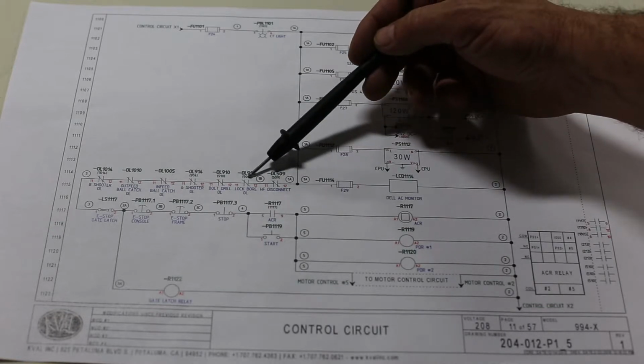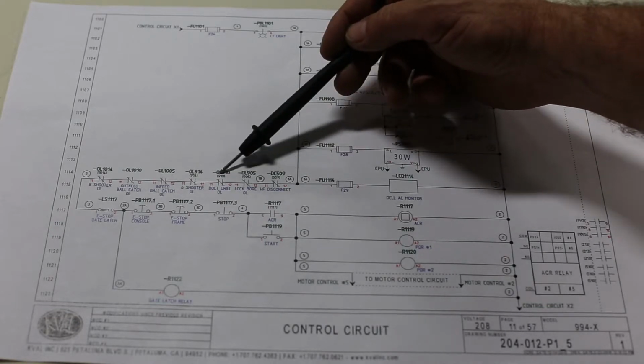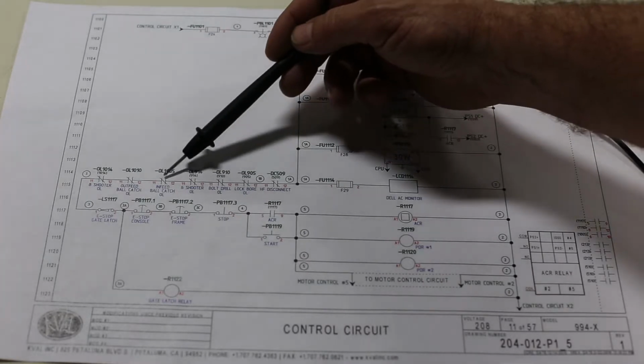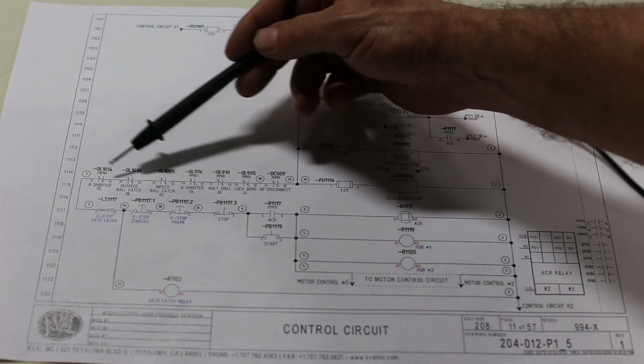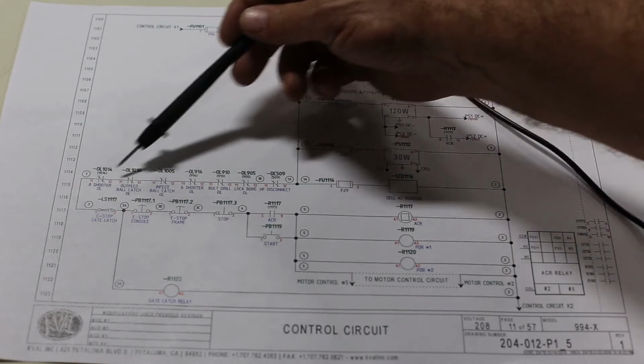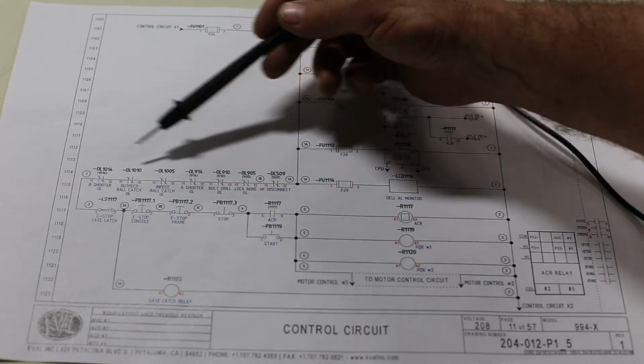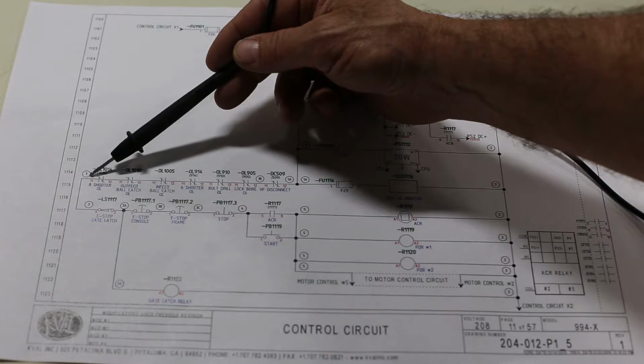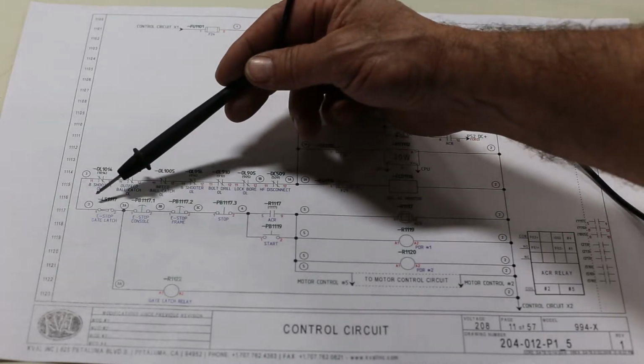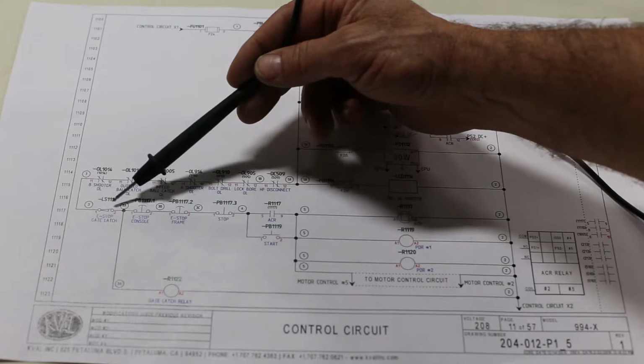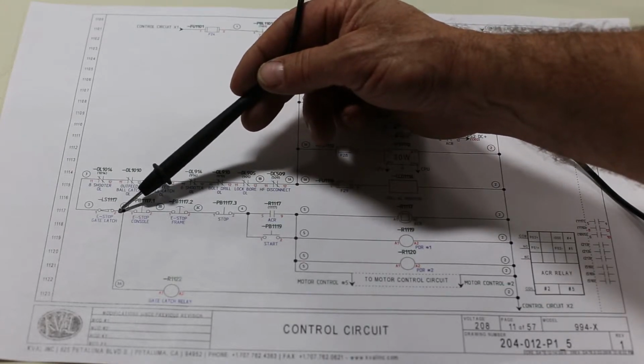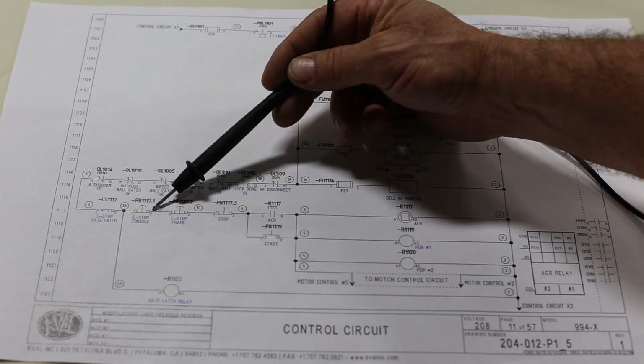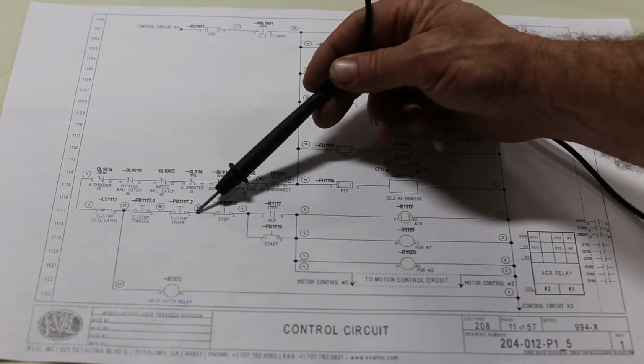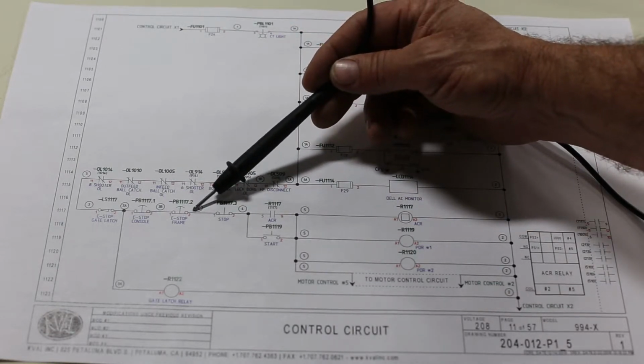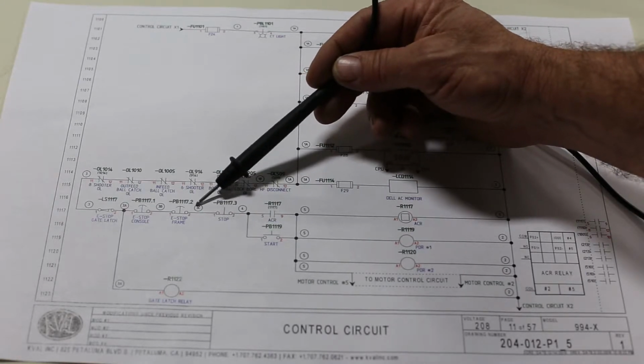And then we go to the overload for the lock bore, the bolt drill, the 6-shooter, the ball catch on the in feed, the ball catch on the out feed, and the 8-shooter. Once we get all of these overloads activated, we get number 3 over here. Then we start our E-stop circuit, where we start with 3, and we go to the gate latch on the back side of the machine, and then there's a push button on the console, and then there's an E-stop between hinge 1 and 2 on the 990 example that we have here. Once we get that, we got our 3C.